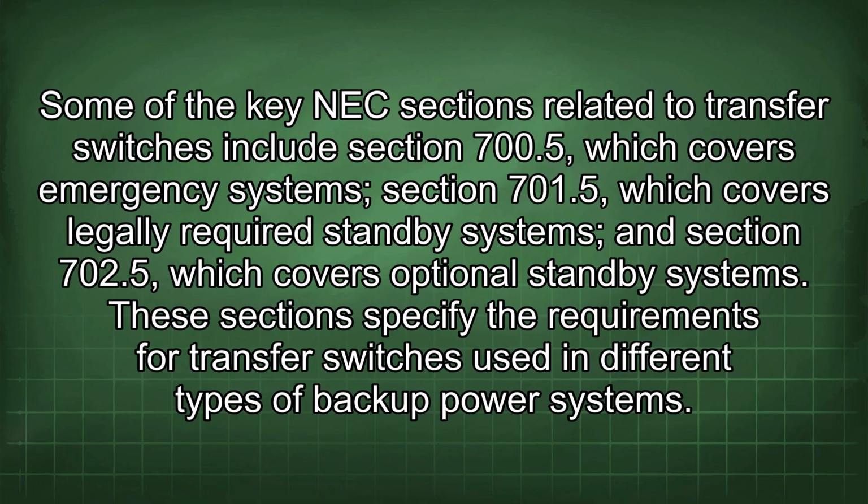Some of the key NEC sections related to transfer switches include Section 700.5, which covers emergency systems, Section 701.5, which covers legally required standby systems, and Section 702.5, which covers optional standby systems. These sections specify the requirements for transfer switches used in different types of backup power systems.